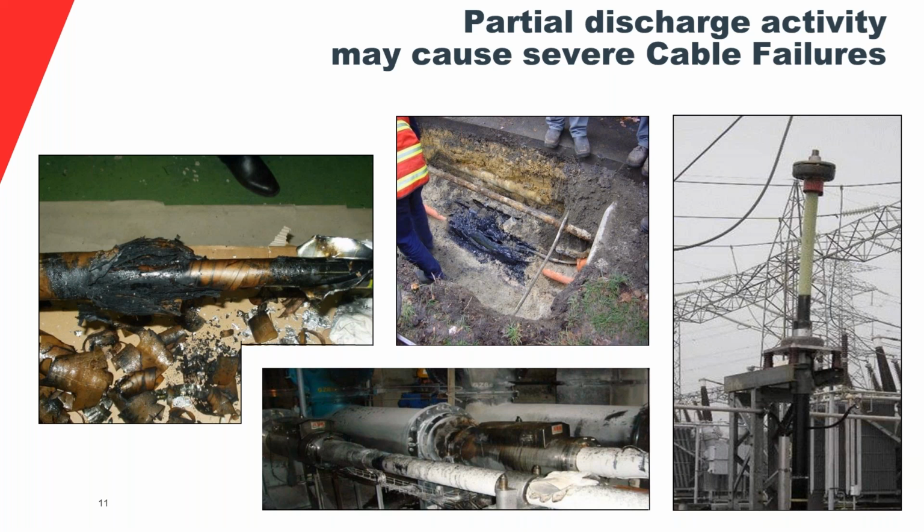In this case, it was porcelain, if I remember correctly. That end termination had partial discharge in it, and it just exploded. And that was in an urban area. It was a big explosion, and everybody was lucky that nobody got hit, just people walking by, because even though you have fences and everything, in an urban area everything is dense and close.